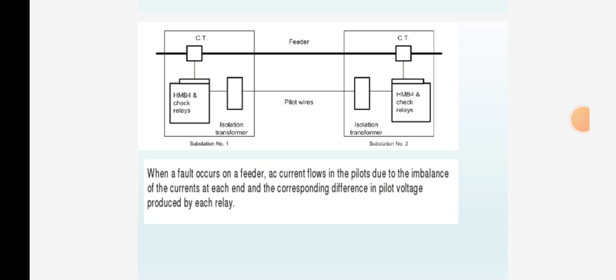Under normal conditions and in case of external faults, the secondary currents are equal and circulate in the pilot wires. The differential current of the two current transformers is zero and the relay does not operate. During internal faults, this balance is disturbed and differential current flows through the relay operating coil.